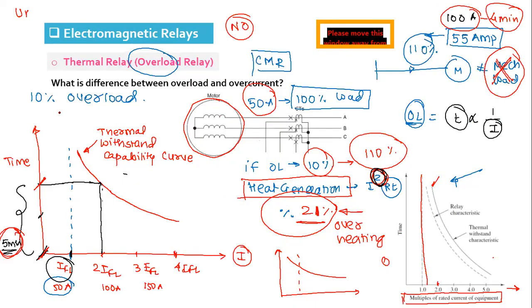What is time? Still we have 5 minutes, so I will end here after this point. Higher the current, lesser will be the time it can take. So the thermal withstand capability curve has this nature. I hope it is clear why the withstand characteristic follows the inverse square proportion, as heat generation is proportional to that.